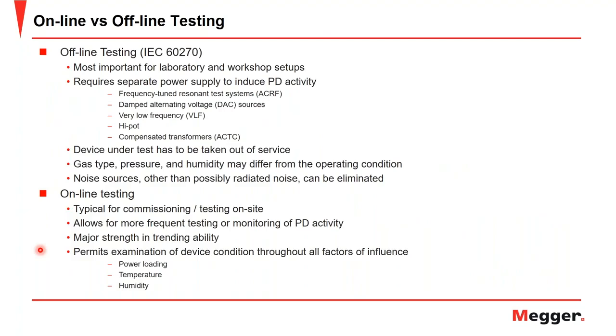So when we talk about testing, testing for partial discharge can be done either online or offline. When partial discharge testing is done online or offline, we typically talk about the IEC 60270 method. And this is mostly important for laboratory and workshop setups. Because the apparatus is offline and the test is done offline, this does require a separate power supply to induce the PD activity. This can come in the source of resonant test systems, damped alternating voltage sources, very low frequency VLF sources, hipot, and step-up transformers. As stated, in the offline test the device under test has to be taken out of service, which can affect operating conditions such as gas type, pressure, and humidity that may differ from online testing. But one of the things you gain is that noise sources other than the radiated noise can be eliminated.